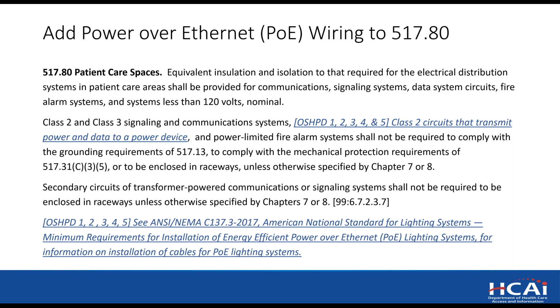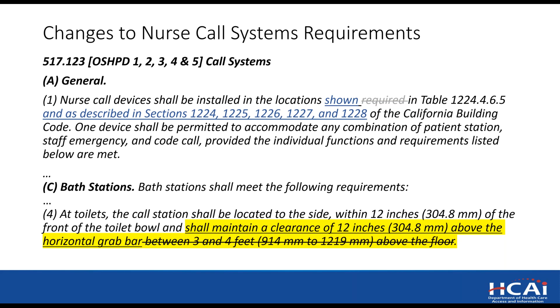Changes to the nurse call system. On the top, we're just adding in that there are different nurse call requirements described. 1224 is for OSHPD 1, 25 OSHPD 2, 26, 3, 4, and 5. And then on the bottom, I think something that should help everybody out, we've revised the location of the Bath stations. They used to be required to be within 3 or 4 feet of the ground. Now the new requirement is to maintain a clearance of 12 inches above the horizontal grab bar. We had some conflicts of meeting this code previously, and so we've adjusted it accordingly. Next slide.